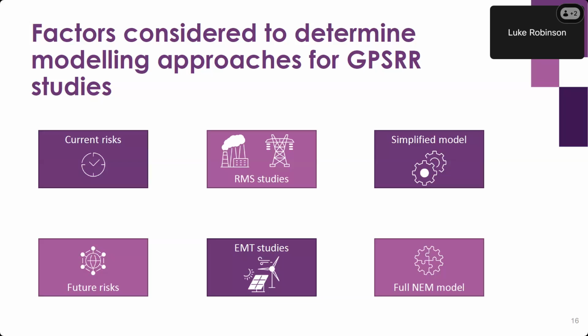because it'll be more time efficient and it should be sufficient as well. Finally, in our study approach, we've also got a simplified model and a full NEM model that we can choose from. Because the GPSRR is a yearly process to identify risks, develop models, perform studies, and analyze and report on the results, we need to have a focused effort on where we can get the best return on investment of our time for the year. So for studies that require high accuracy, we're likely to study a small number of cases in the full NEM model, but due to the added detail, it'll take longer to develop the cases, tune them, run them, analyze them, etc. But if we'd prefer to do a larger number of screening studies or things that are primarily frequency based, then the simplified model may be more appropriate.